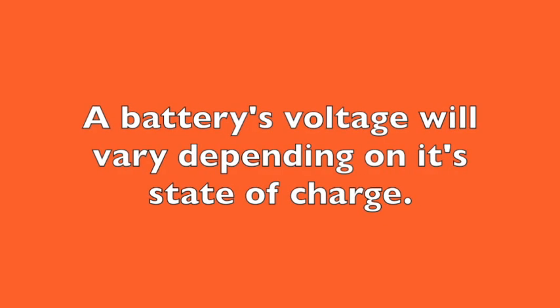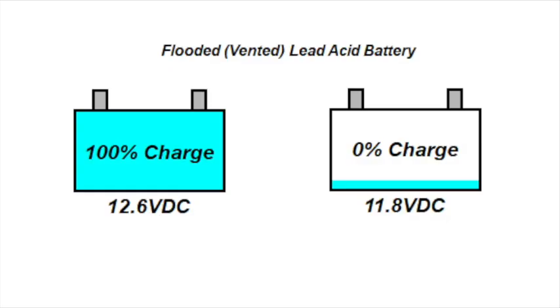When a flooded, that is vented, lead acid battery is 100% charged, it will have an open circuit voltage of 12.6 volts DC. When it is fully depleted with 0% charge, the voltage will be around 11.8 volts DC.